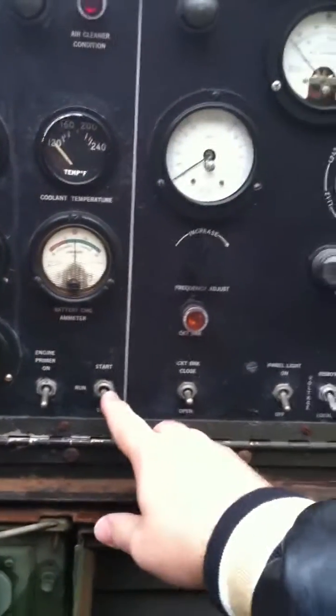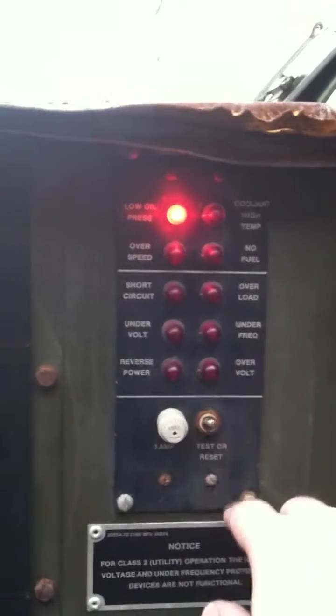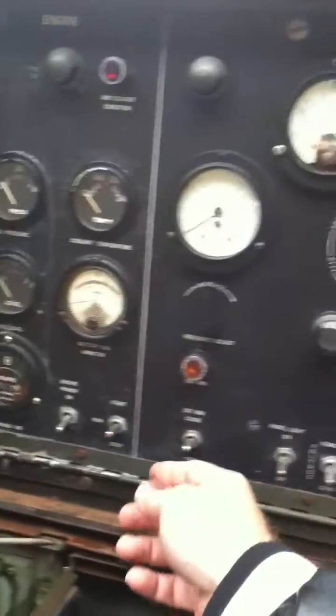This is how you adjust the throttle on this version unit. So what we're going to do is go through our setup. Click your run switch on, check out your gauges. Let's go to test to make sure your safety circuits are all 100%. Low oil pressure is always on naturally because the engine is not running. Let's give it a shot — go ahead and hit start. And that's it.